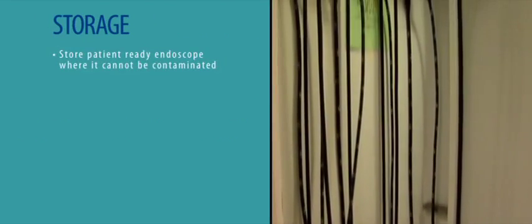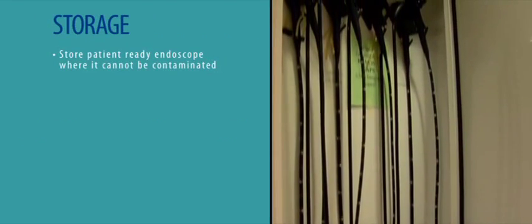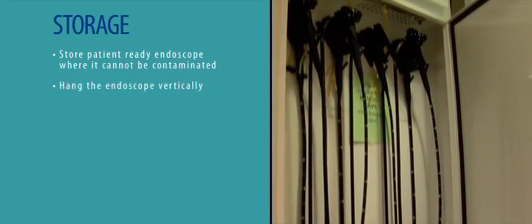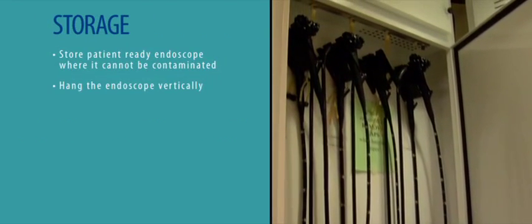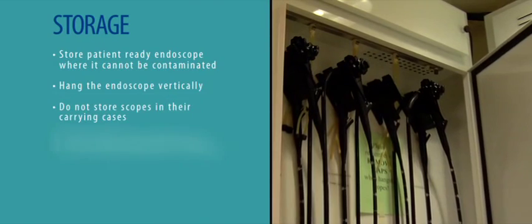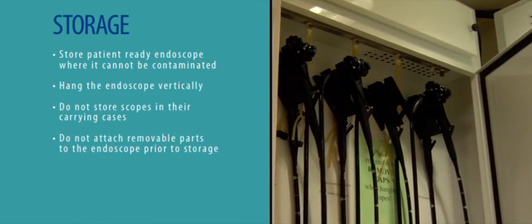8. Storage. The patient-ready scope should be stored where it cannot be contaminated prior to its next use. Hang the endoscope vertically in a clean, well-ventilated, dust-free area. Do not store scopes in their carrying cases. Do not attach removable parts to the endoscope prior to storage.